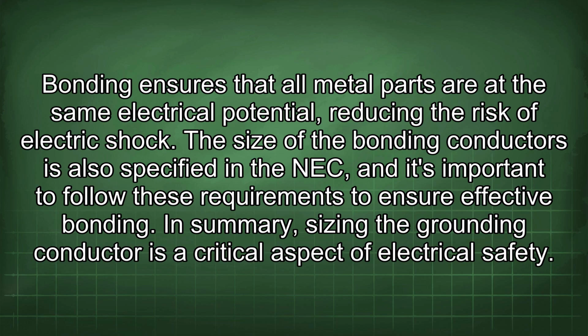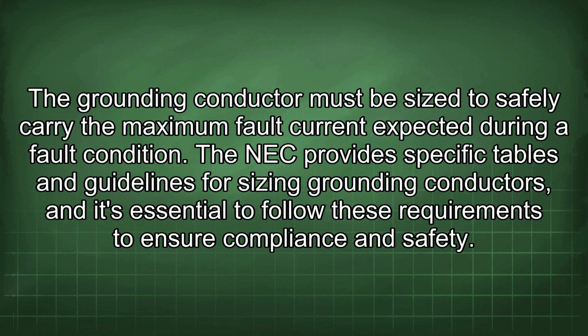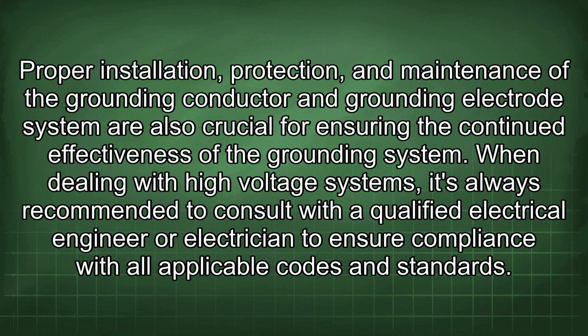In summary, sizing the grounding conductor is a critical aspect of electrical safety. The grounding conductor must be sized to safely carry the maximum fault current expected during a fault condition. The NEC provides specific tables and guidelines for sizing grounding conductors, and it's essential to follow these requirements to ensure compliance and safety. Proper installation, protection, and maintenance of the grounding conductor and grounding electrode system are also crucial for ensuring the continued effectiveness of the grounding system.